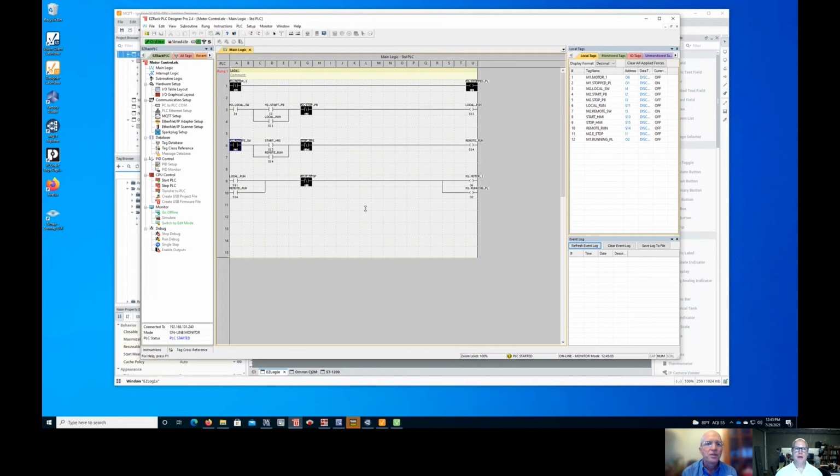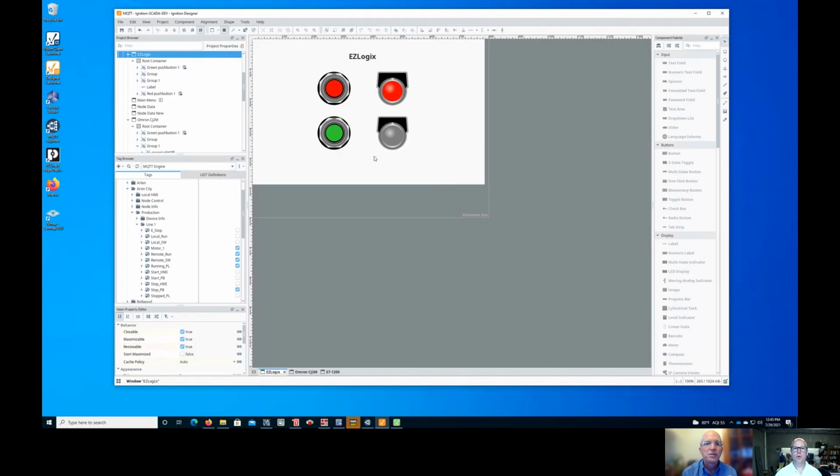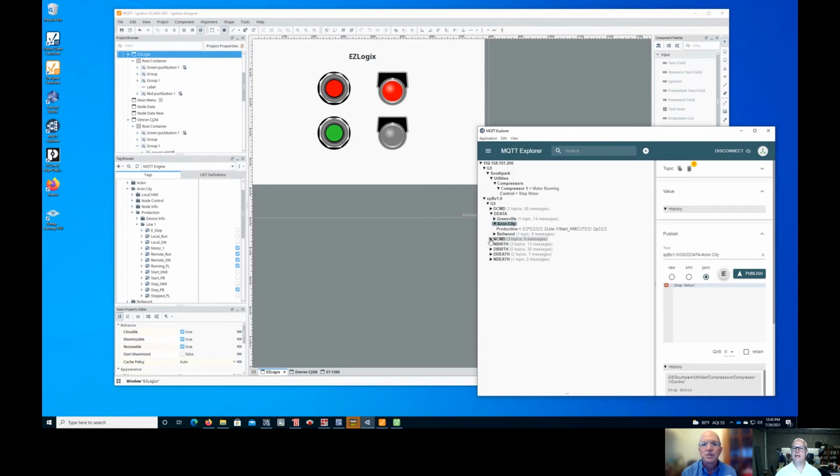Now, as we talked about, this is controlling over Sparkplug B. So the connection that I have here, this is all connected to a broker. I'm now sending out a command that you can't see. Let's go back over here to the broker. You'll notice there are now also these commands that show up. And now you can see that there are commands going back and forth. So this is all part of that Sparkplug B specification, that you'll have data and you'll have node commands. You'll also have device commands coming back over. Just depends on what's working.